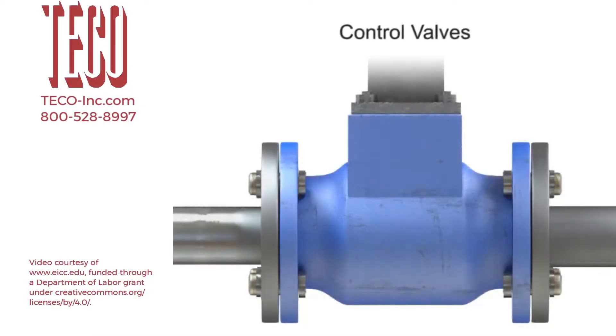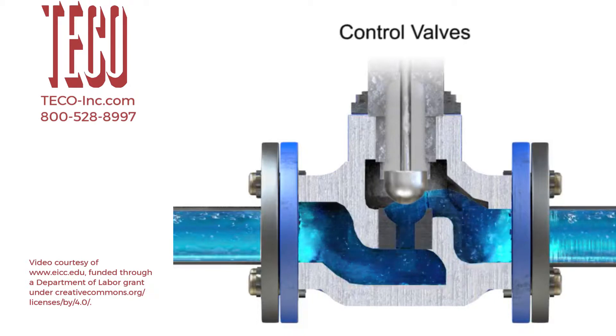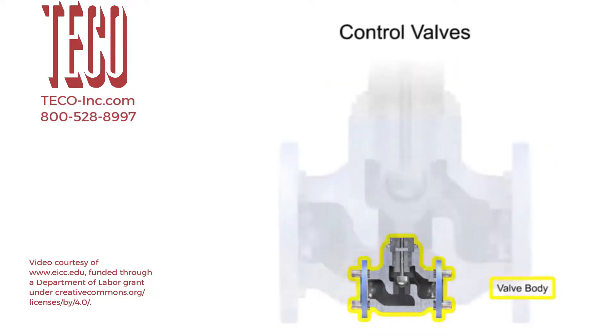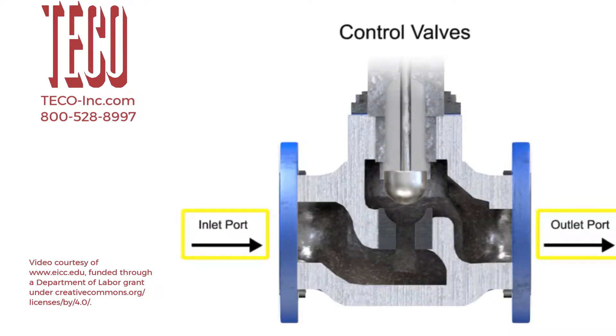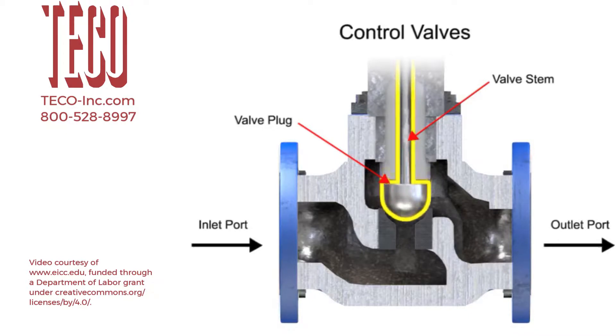Control valve actuators control fluid in a pipe by varying the orifice size through which the fluid flows. Control valves contain two major components: the valve body and the valve actuator. The valve body provides the fluid connections and a movable restrictor comprised of a valve stem and plug that is in contact with the fluid that varies the flow. The valve actuator is the component that physically moves the restrictor to vary the fluid flow.